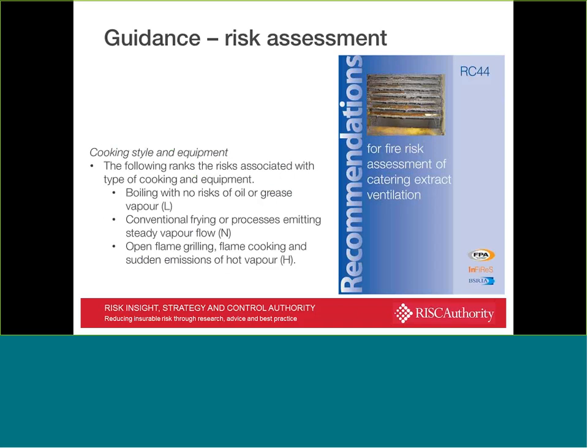The document was really designed to support the fire risk assessor or the insurance surveyor in looking at systems and being able to make a judgment as to whether it was good, bad or indifferent, or certainly was in a position that needed some remedial treatment. And I've just put some example text there, which just shows you how the document flows. So in addition to the guidance that's provided, there are also a series of checklists which you can use, which enable you to understand whether the system you're looking at represents low risk, a normal risk, or a high risk, in very, very simple and crude terms.